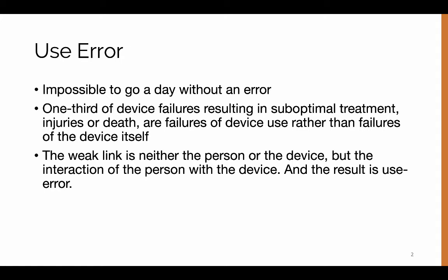And I think it's important for us to all recognize that as humans, it's pretty much impossible to even go a day, probably even an hour, without making an error. And in fact, 1/3 of device failures in medical devices that result in suboptimal treatment, injuries, or death tend to be failures of device use rather than failures of the device itself. That is, the piece of equipment actually didn't fault. It turns out the person using the equipment ended up creating a fault, and that ended up causing some kind of untoward consequence.